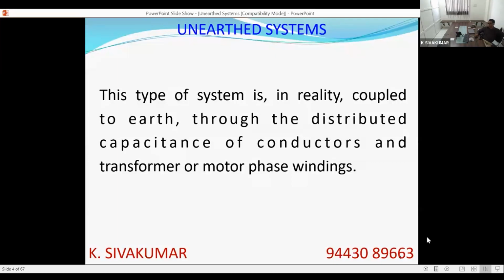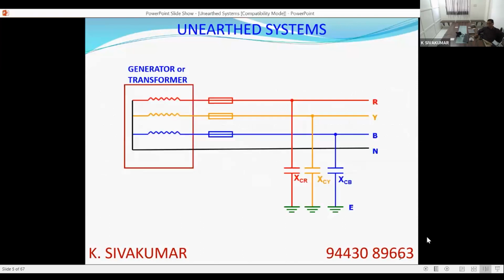There will be a capacitive coupling. Any conductor, even if you take a cable, there will be a conductor and armor, and in between there will be a dielectric. So wherever there are two conductors and a dielectric, there will be capacitance formed. In fact, all unearthed systems are capacitively coupled earthed systems only, to be more precise. So this will be like this. R phase with the earth will have an XCR, Y phase to earth will have an XCY, blue phase to earth will have an XCB. This capacitance will be there in the system. Capacitive coupling will be there.